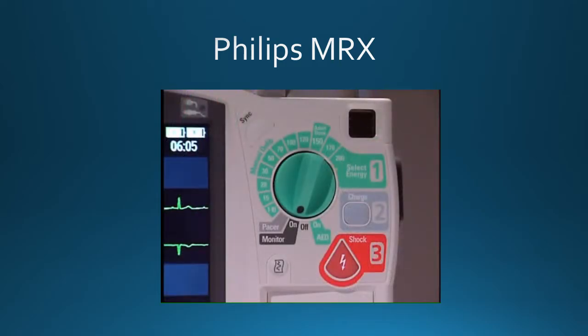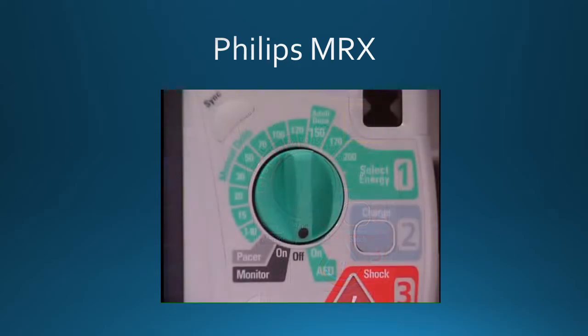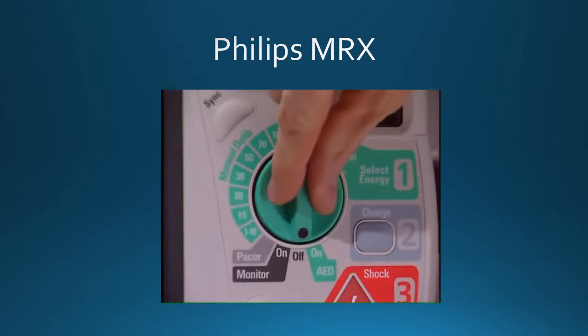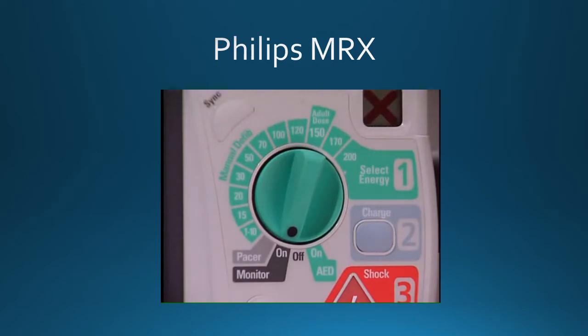Operating controls and indicators are on the front. This is the ready-for-use indicator. The flashing hourglass tells you that the device passed its last self-test and is ready to go with sufficient battery power for defibrillation, pacing, and ECG functions. The therapy knob is the on-off switch. Just turn it to the desired mode of operation.